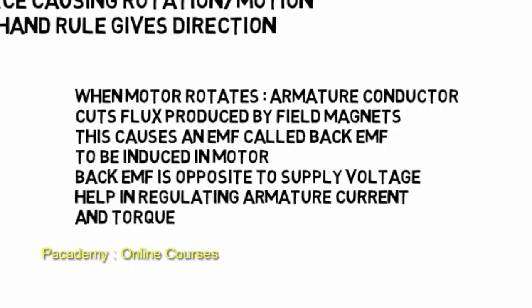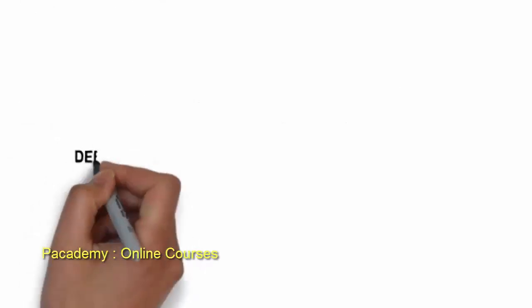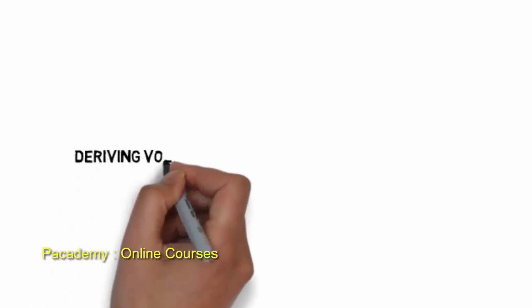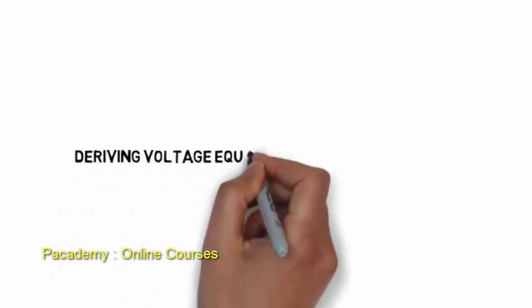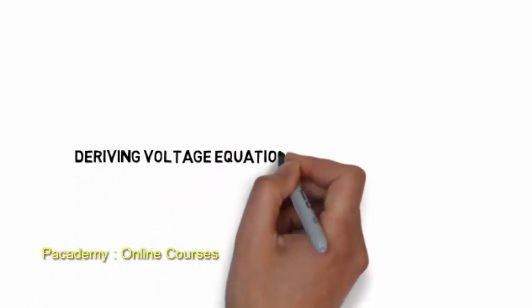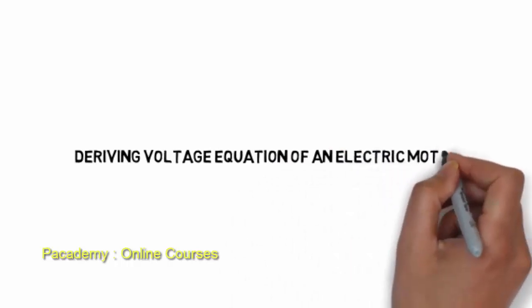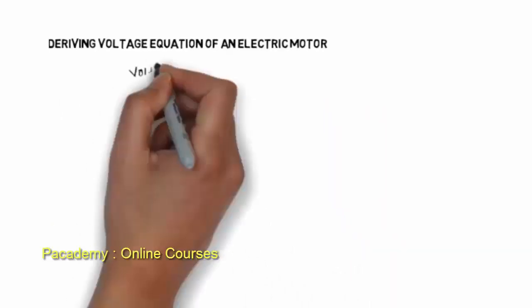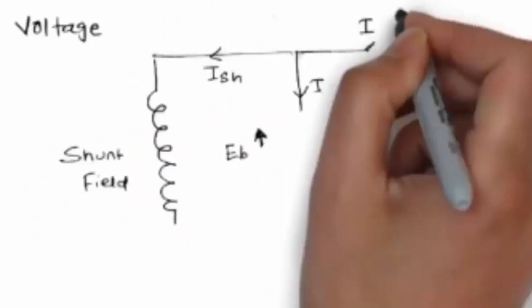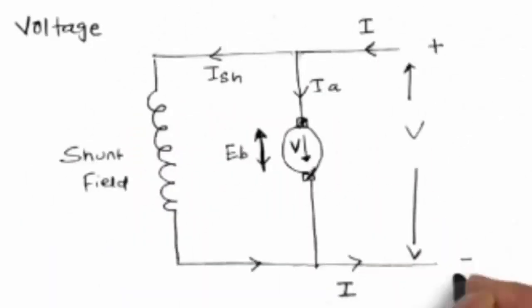According to the generator principle, an EMF will be induced in the conductor. This EMF is called back EMF, and the back EMF will always be opposite to the supply voltage. The armature current is given by supply voltage minus back EMF, divided by armature resistance. In this way, the back EMF helps to regulate the armature torque and current.